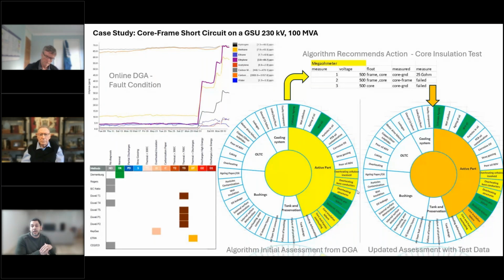We can see above in the table where the yellow arrow is pointed, that 2 of the tests failed, indicating a short between the frame and the core. Then, it's pretty intuitive at this point, but you can take this tool and feed that data back to it, and it diagnoses again. Clearly there's a core insulation failure with a higher degree of confidence that that's the identified failure mechanism.